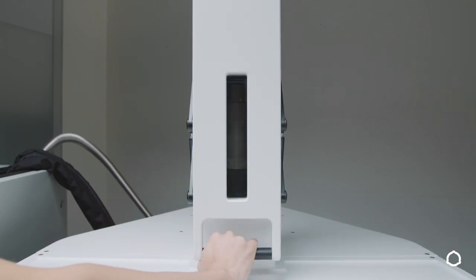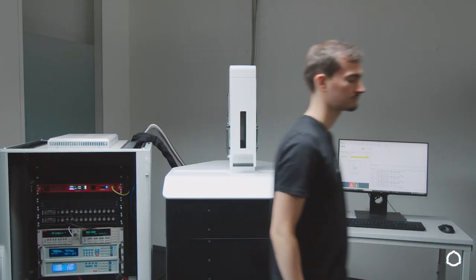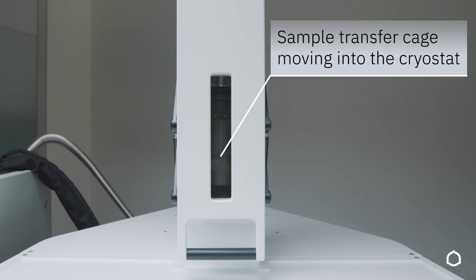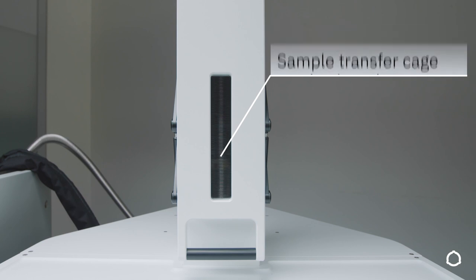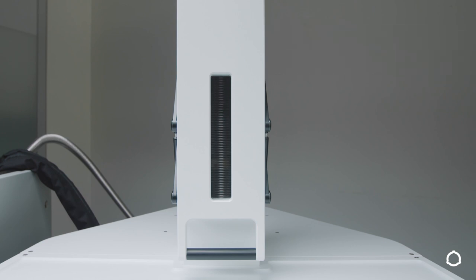Once sufficient vacuum conditions are reached, the gate valve is opened and the cage is loaded into the cryostat. The puck is firmly mounted onto the sample stage and automatically detached from the transfer cage. The system is now cooling the puck down to the base temperature and is ready to perform measurements.